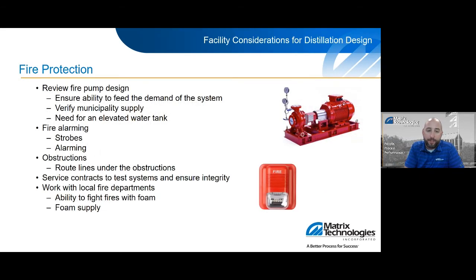Some other considerations for your facilities on fire protection is your fire pump design. Depending on what system you select, water or foam, you want to make sure your pump has the capability to meet the demand. As I just mentioned, you've got the 120 minutes of supply that you need for a wet system, so that's pretty taxing on a system. So you want to make sure you check that supply pressure that your municipality can supply to you, and if that pressure is not adequate enough, which is oftentimes the case, an elevated water tank may be required to meet those needs.